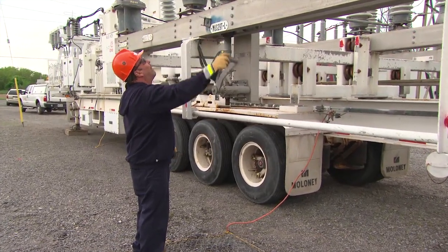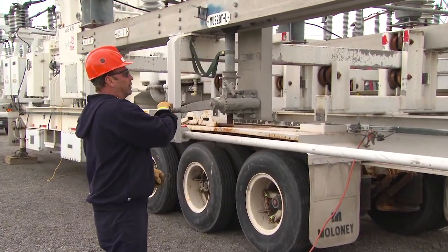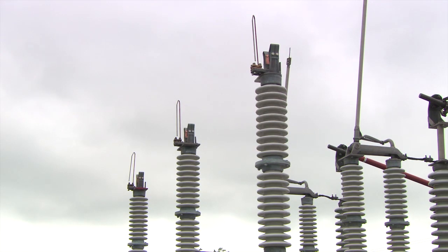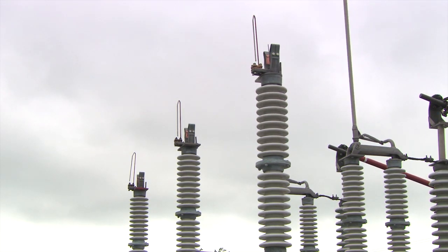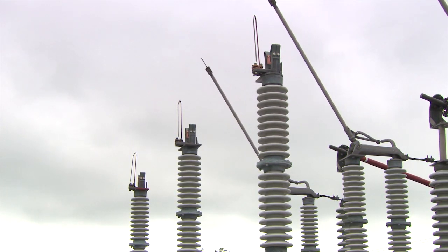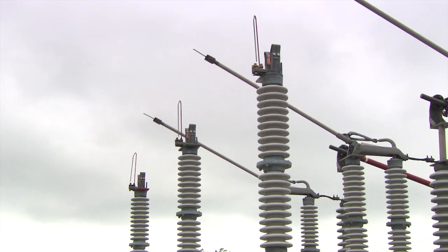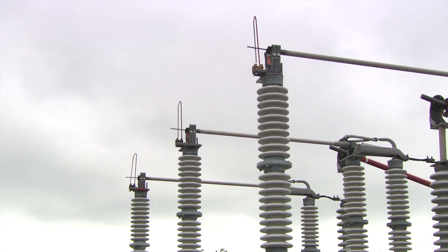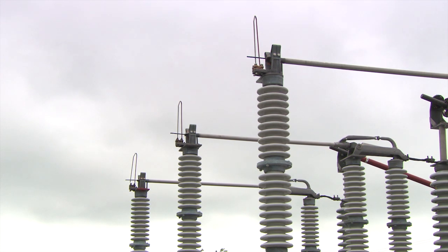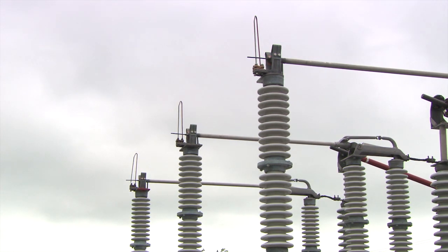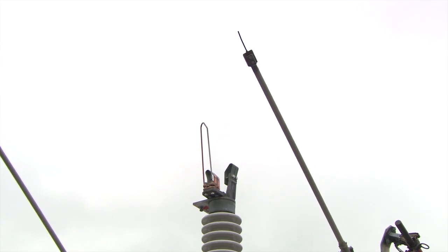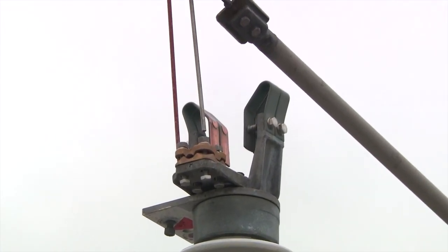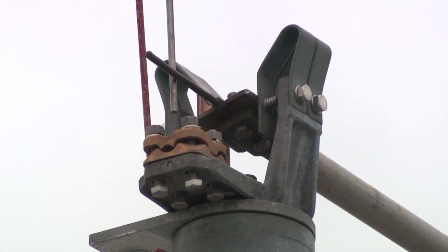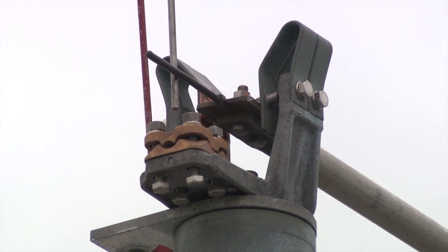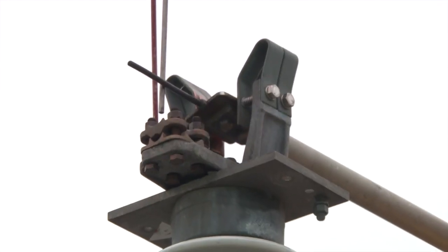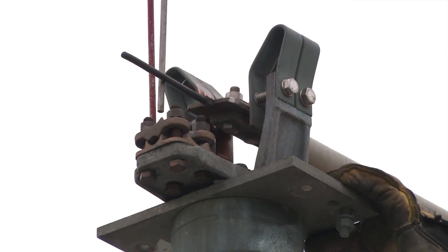While standing on the ground mat, test operate the switch closed, checking that all 3 phases touch the respective arcing horns at the same time before settling into the jaws. The main moving contact should be centered when entering the main contact jaw. The moving contact should turn and compress the main contacts. All moving contacts should be within 5 degrees of horizontal.